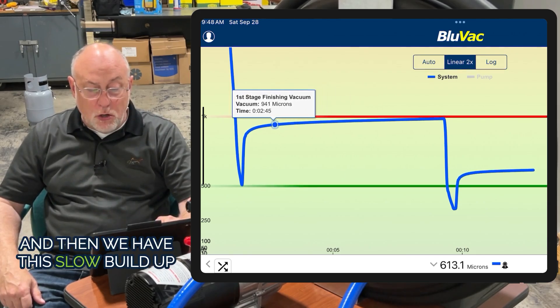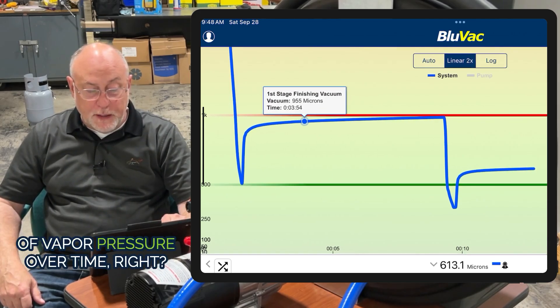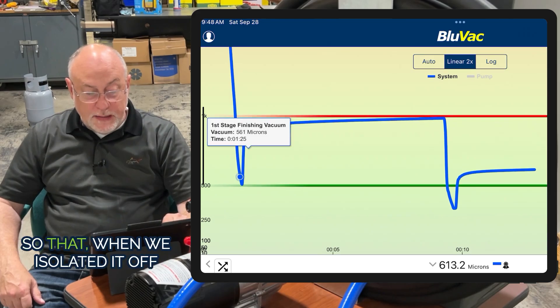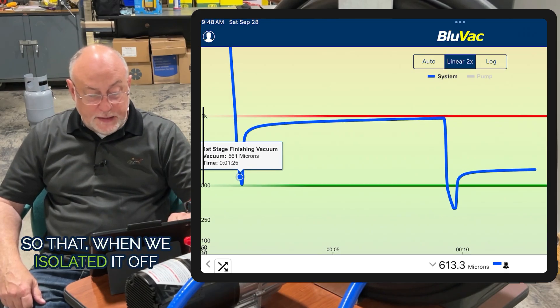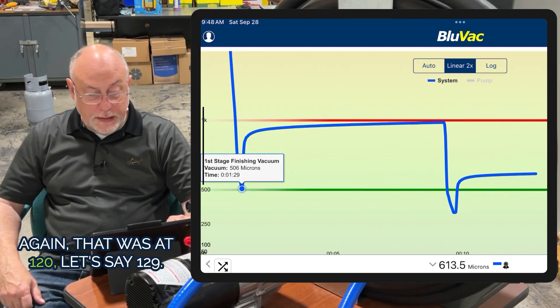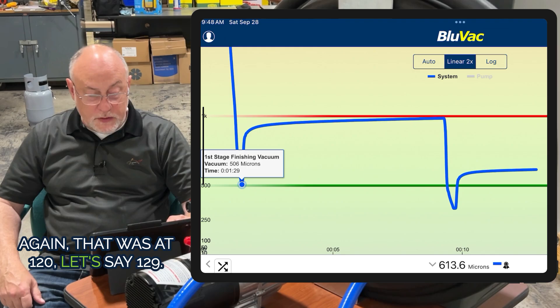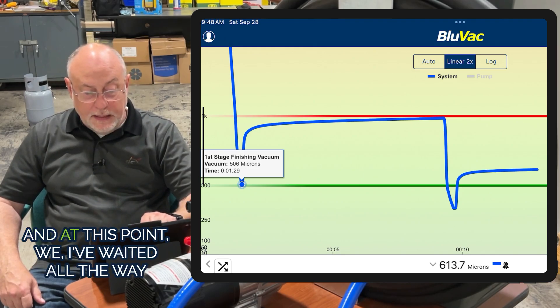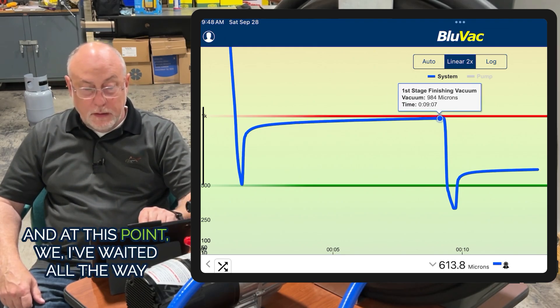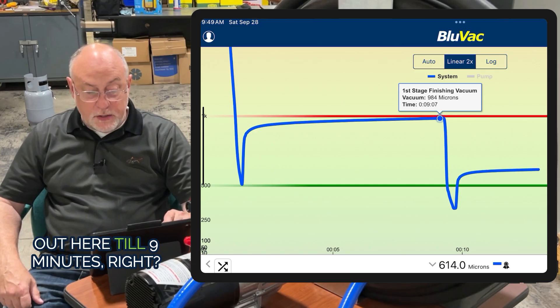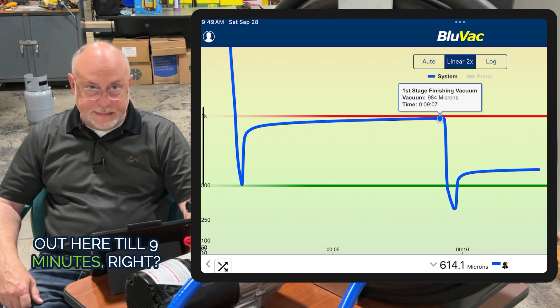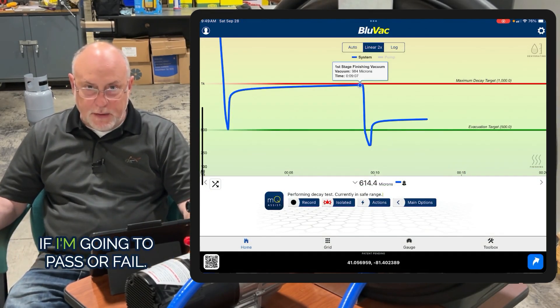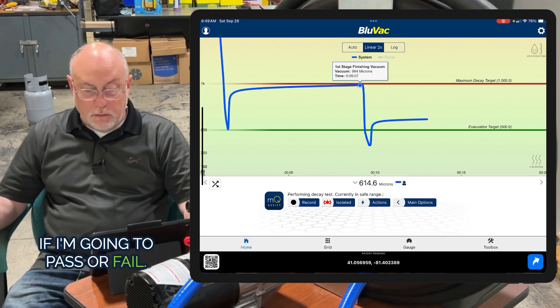Then we have this slow buildup of vapor pressure over time. When we isolated it off again, that was at 1:29. At this point, I've waited all the way out to nine minutes - eight minutes in decay to determine if I'm going to pass or fail.